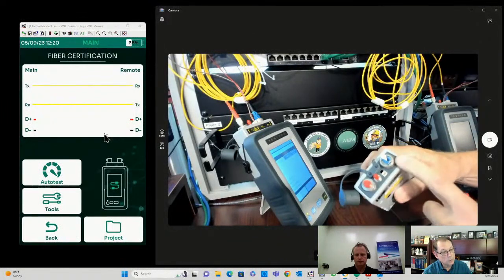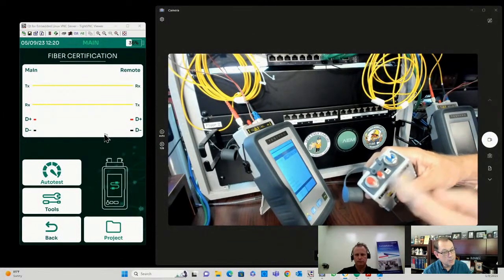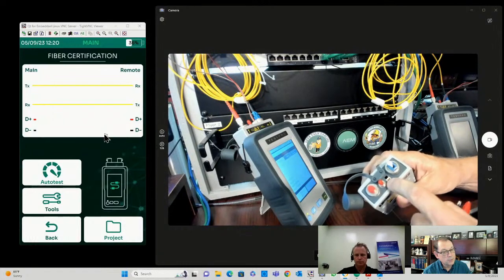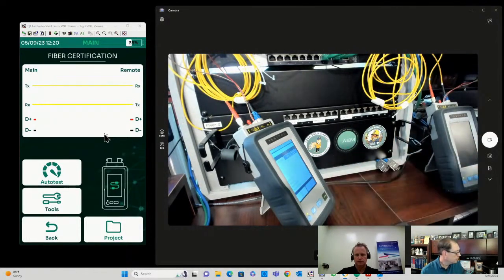We've got a light source port and a power meter port, and we've got that at both ends, so we're doing a bidirectional test. And here's a little electrical connector that this jumper plugs into, and what we do is connect those clips.